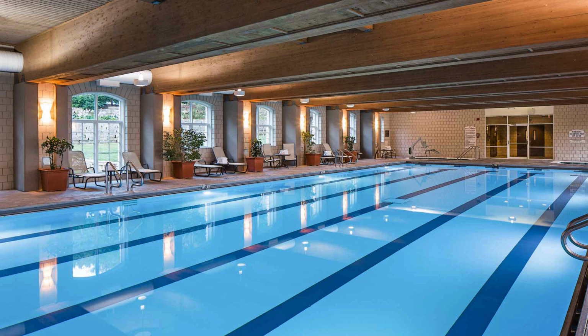There are several types of HVAC systems specifically designed for indoor pools. Desiccant dehumidification systems. These systems use a desiccant material to absorb moisture from the air. The desiccant is then regenerated by heating it up, which releases the moisture back into the air outside the pool enclosure. Pool air handlers, PAHs. These are specialized air handling units that combine heating, cooling, dehumidification, and ventilation capabilities. PAHs often use chilled water coils to cool the air and a desiccant wheel to remove moisture.